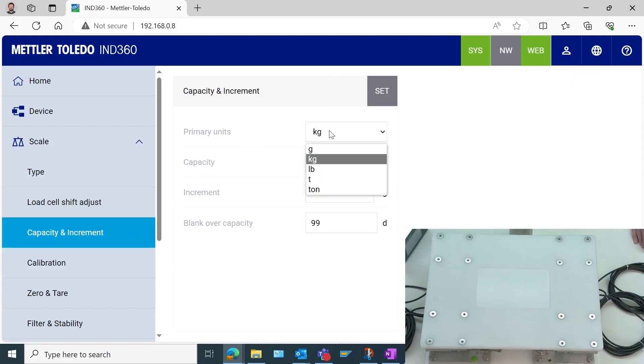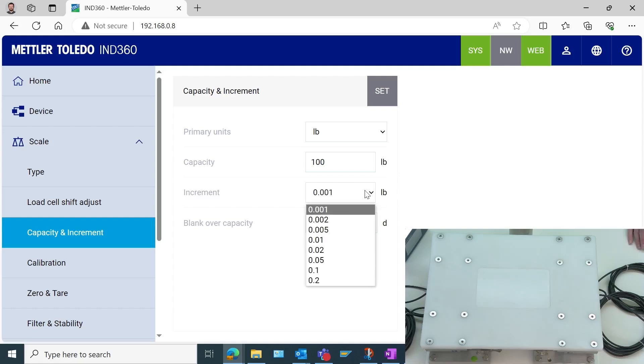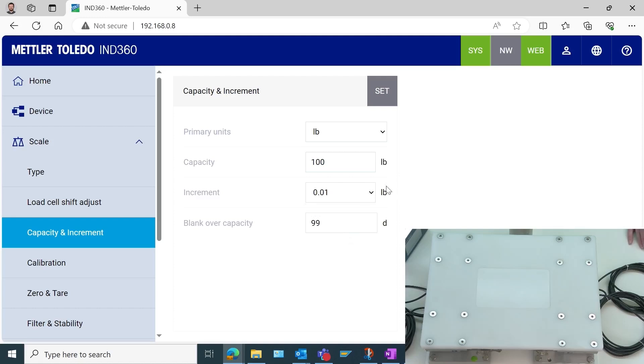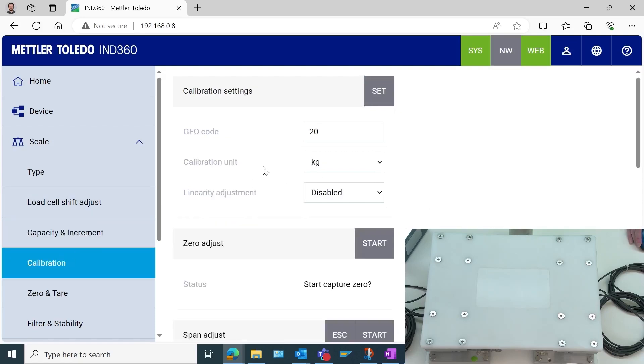Since I happen to be in the U.S., I will set my units to pounds, and my capacity will be, let's say, 100 pounds in this case, and I only need 0.01 increment value. We're going to make sure we select set, otherwise those units will not be written to the IND 360. And we'll continue on to the next tab, which is the calibration.